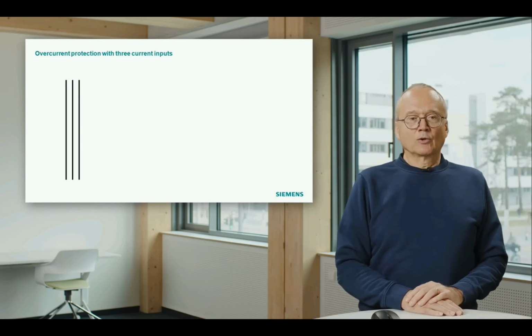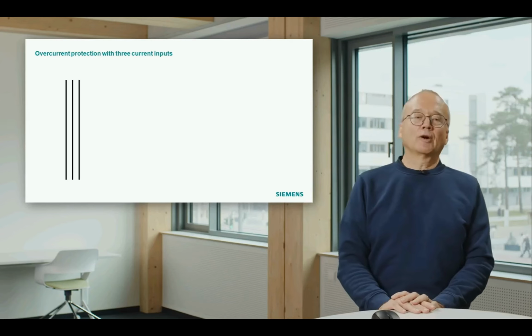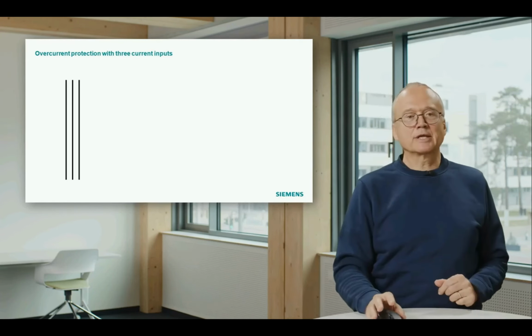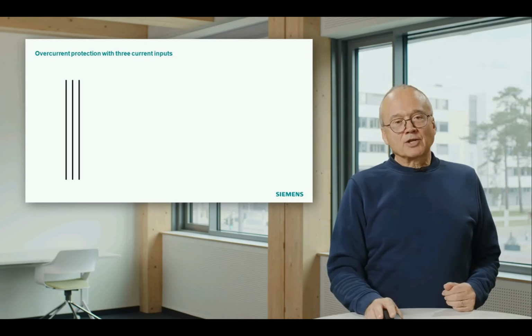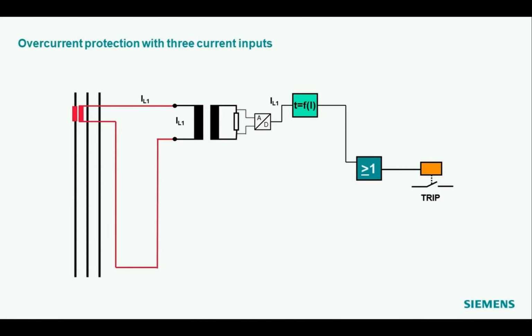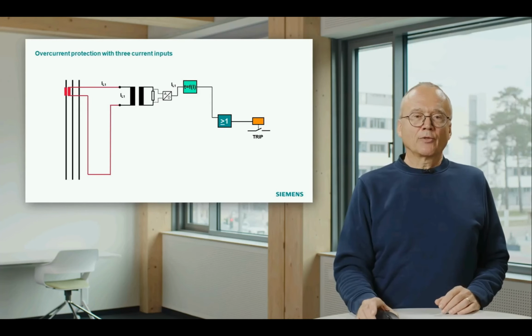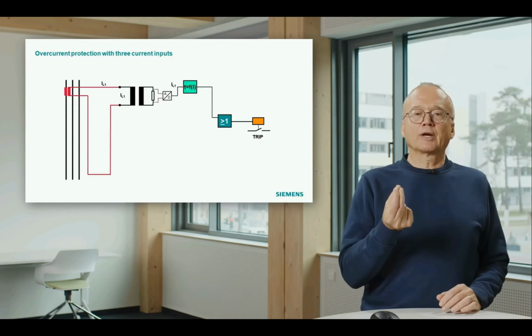So how does an overcurrent protection look? Let us start with the three phases of our protected line or cable. They are shown here. And now we measure the current, only the current, by using this current transformer, and we connect this current transformer to our protection relay. I draw here parts of a protection device. You see here an input transformer. That's a measuring input, the connection point where the relay measures the current which comes from our current transformers. Then we have a shunt, A to D conversion, some algorithms that calculate the current. And then somewhere in the digital system, we have the amount of current we see.